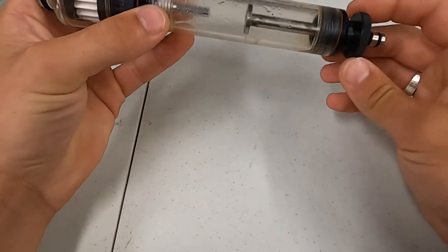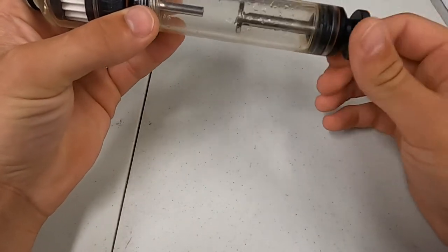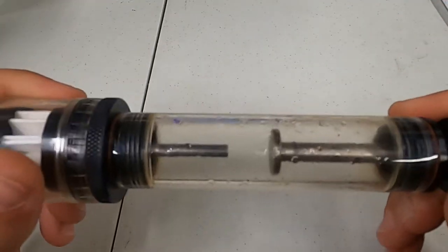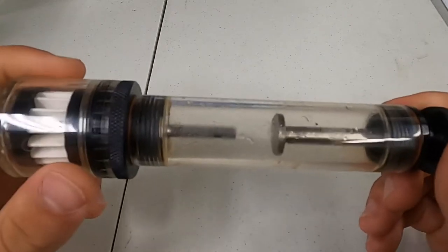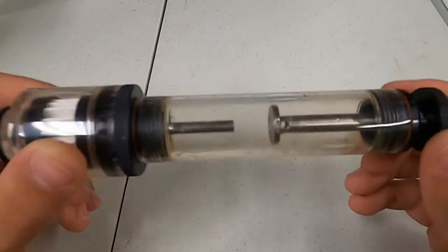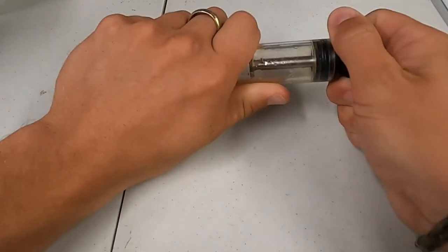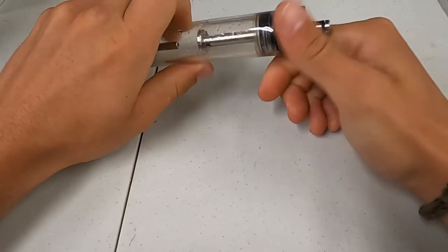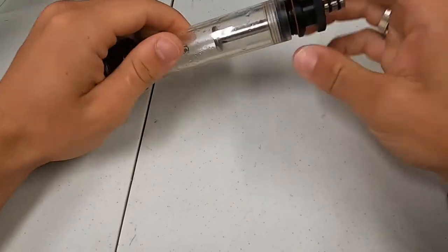It allows for you to see that, okay, clearly there's moisture in the sampling, and that's not ideal. You want to recognize that as early on as you can, because it will ultimately damage the internal components of the instrument.